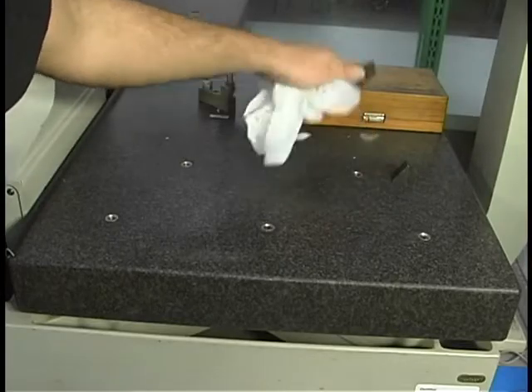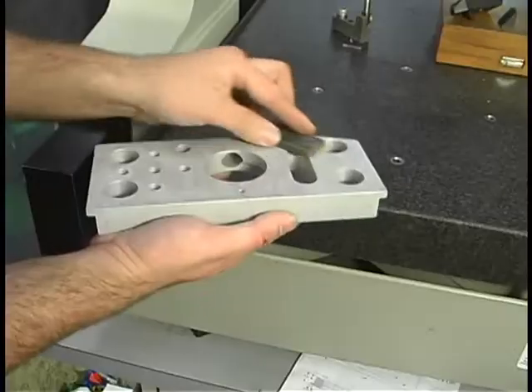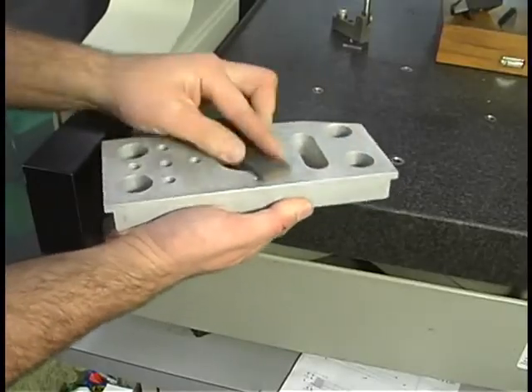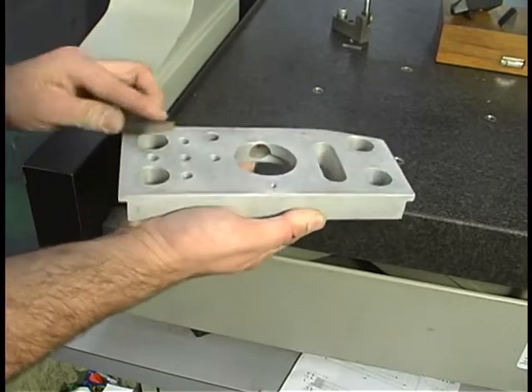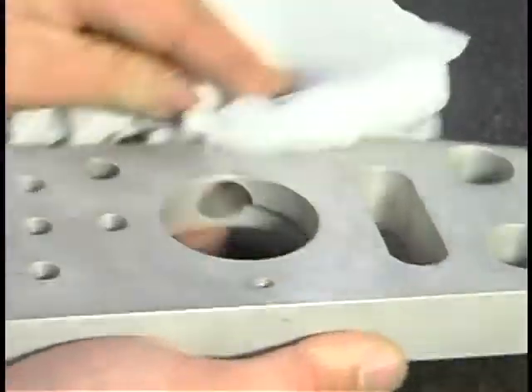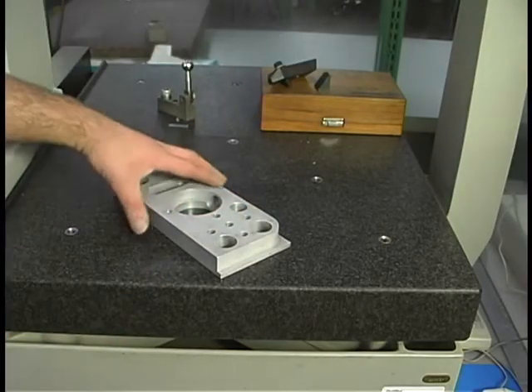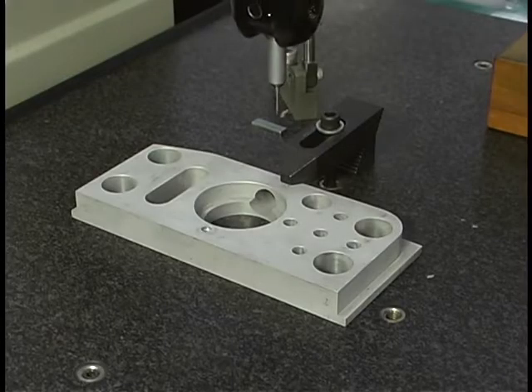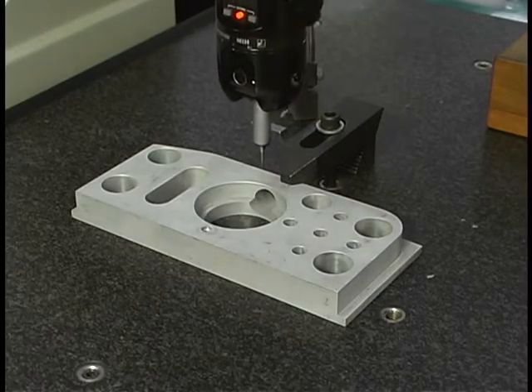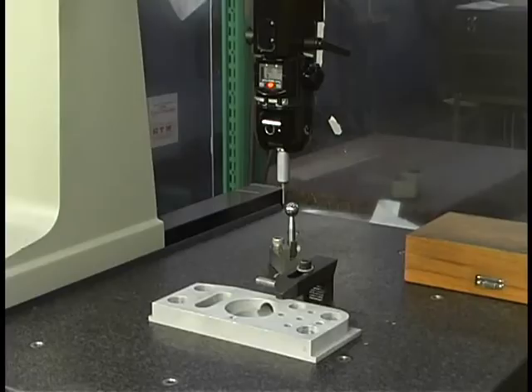Before mounting the workpiece, be sure to clean the surface plate with the proper cleaning material. If the workpiece is going to be placed on the surface plate, the surface of the piece should be stoned to remove any burrs. Then, wipe the surface clean. Locate the piece on the surface plate near the threaded hole to be used for clamping. Be sure the qualification sphere is far enough away to eliminate any possible interference during the measurement. If necessary, move the sphere to another location.